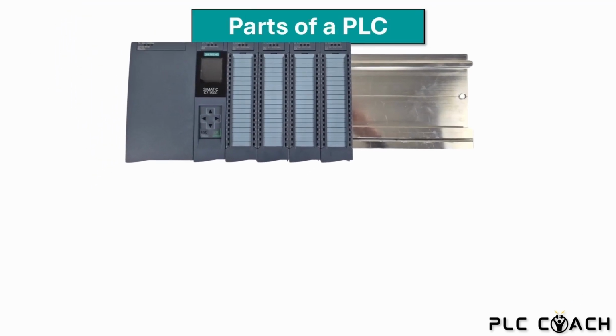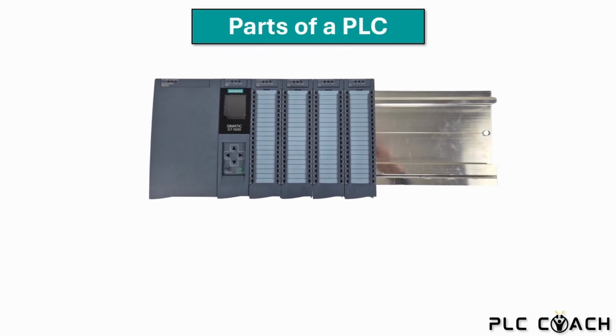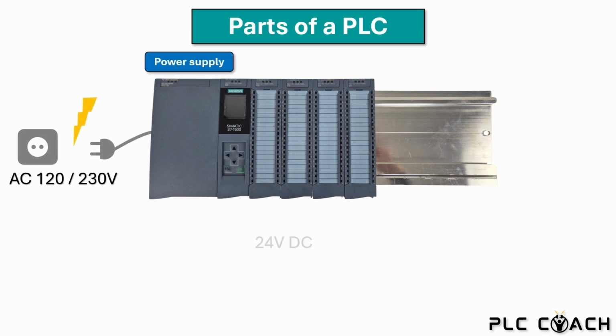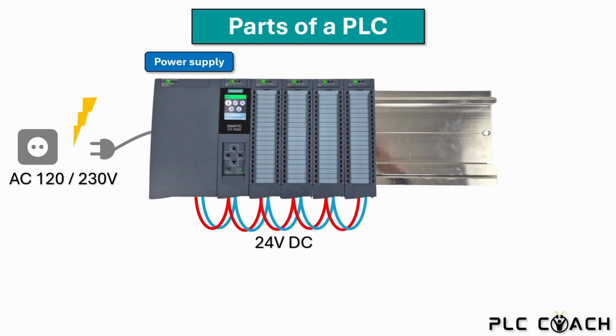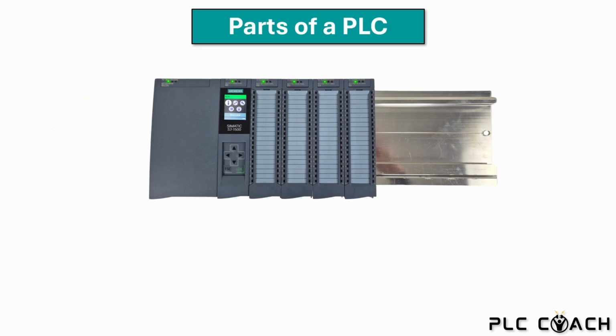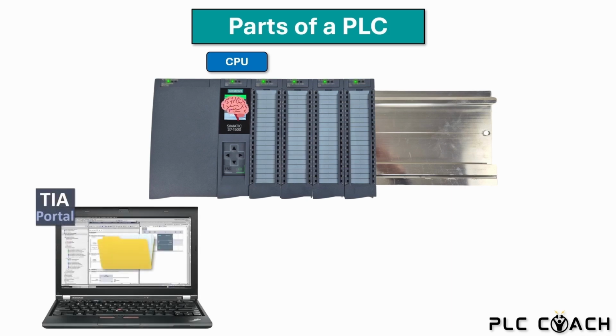Now let's break down the parts of a PLC. I have assembled an industrial control system for us. Here on the left you see the power supply, which converts mains voltage to 24 volt DC for the PLC. Once powered on, the power LED lights up and the CPU display activates. The next part of our PLC is the CPU. The CPU is the brain of our controller. This is where we transfer our project. The connection to the controller is made with a network cable.